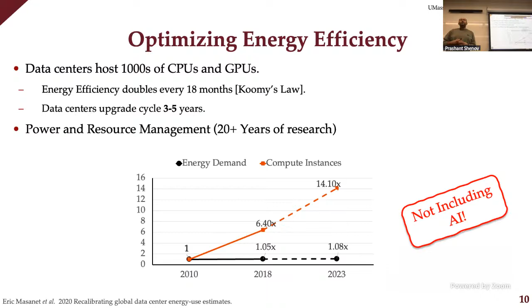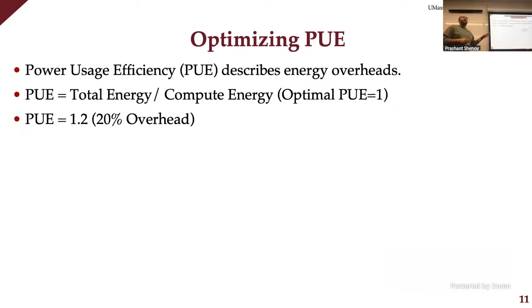Another aspect of data center energy efficiency is PUE, the power usage efficiency, which is the total amount of energy a data center uses over the compute energy. An optimal PUE, where all energy goes toward compute, is 1. So if the PUE of a data center is 1.2, it has a 20% overhead, coming from cooling overhead and power efficiency losses from the grid and transformers.